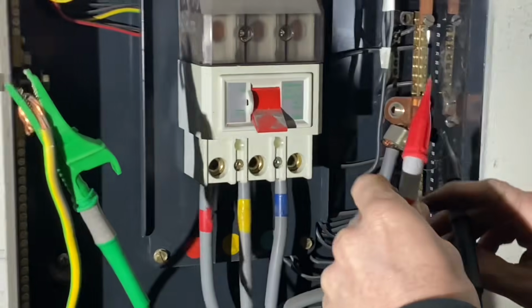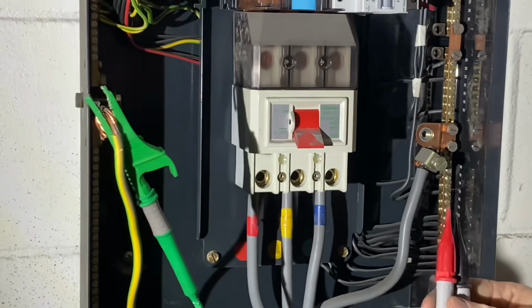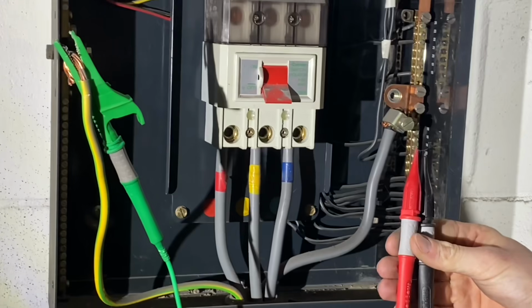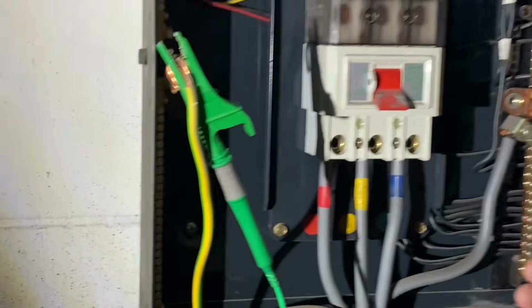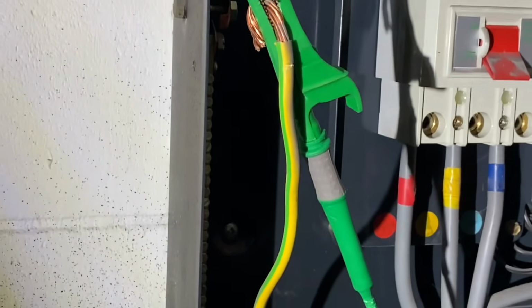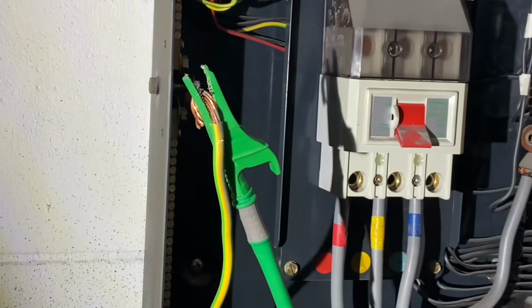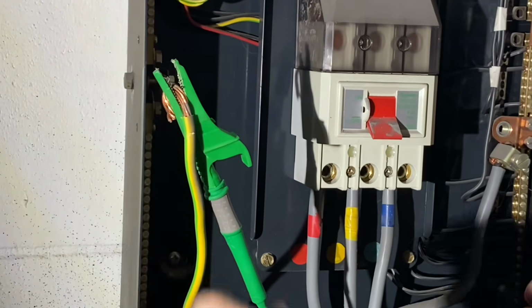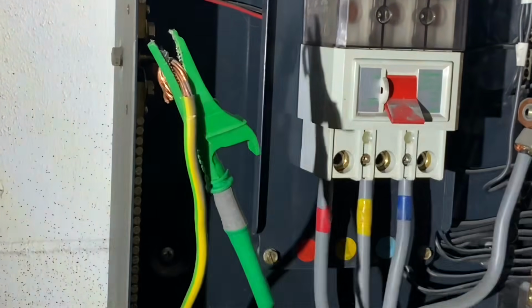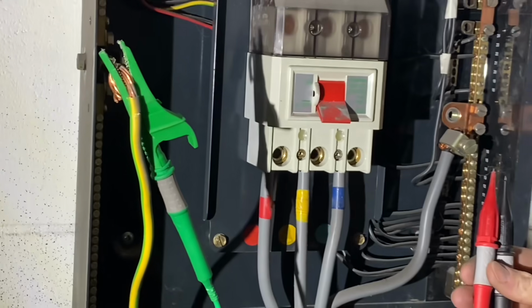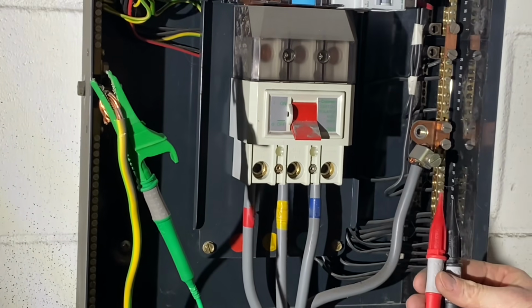So we've carried out the external earth fault loop impedance test there. We've got three readings. You said you're going to record the highest one in your test paperwork. Yeah. Okay, we'll remove the earthing conductor. Just remind me again why we removed that. Purely for parallel earth paths. We want the external earth fault loop impedance, so that is the external earth that goes back to the supply transformer. Good. So that is the one that has to be removed.